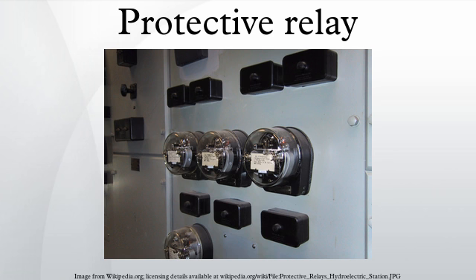A protective relay may respond to the magnitude of a quantity such as voltage or current. Induction types of relay can respond to the product of two quantities in two field coils, which could for example represent the power in a circuit. Although in electromechanical relays calculating the ratio of two quantities is not practical, the same effect can be obtained by a balance between two operating coils, which can be arranged to effectively give the same result. Several operating coils can be used to provide bias to the relay, allowing the sensitivity of response in one circuit to be controlled by another. Various combinations of operate torque and restraint torque can be produced in the relay.